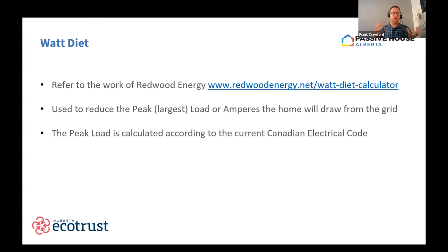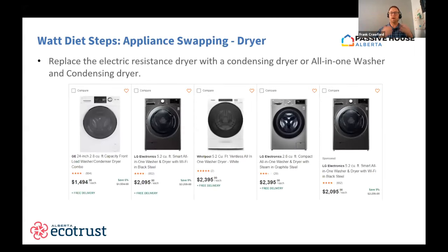And that peak load is calculated based on the current Canadian electrical code, a whole bunch of clauses on that. But using the Watt Diet, you can reduce that peak load. So what are some of the ways? Obviously, if we're electrifying, we are going to be doing appliance swapping.